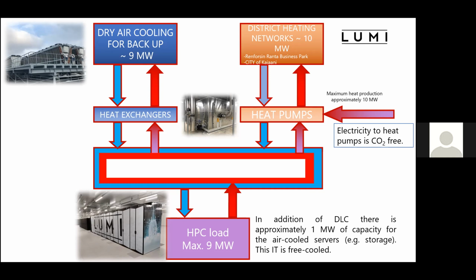The benefit of this area is that the local district heating plant is near, and we can directly use all the waste energy generated in the DLC partition of Lumi. We also have dry cooling as a backup, so we can use free cooling if we have problems with heat pump production.